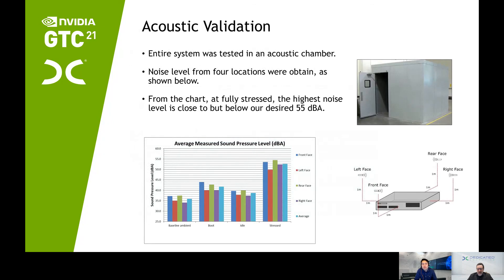One other requirement was that we kept the system less than 55 dB. Under fully stressed conditions, the measured approach was an acoustics chamber. We took four measurements, one meter out and one meter above on all four sides. We measured a baseline in the chamber, then boot, idle, and stress. We expected stress to be our defining level and it measured less than 55 dB. This further validates that this solution is appropriate when a fully stressed system was measured.